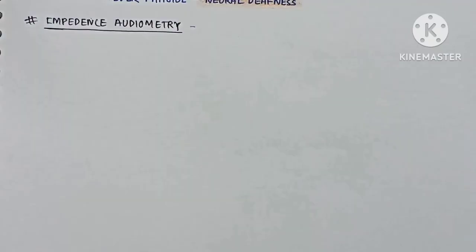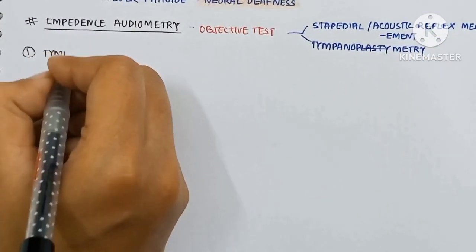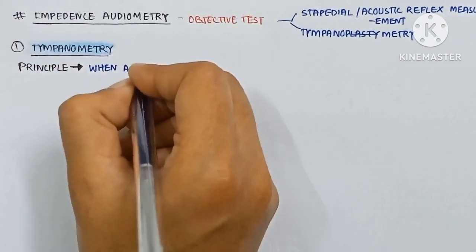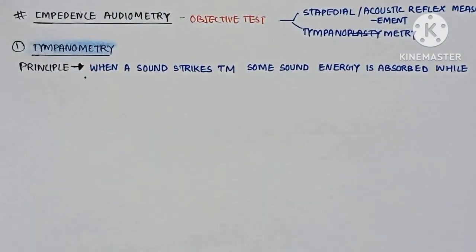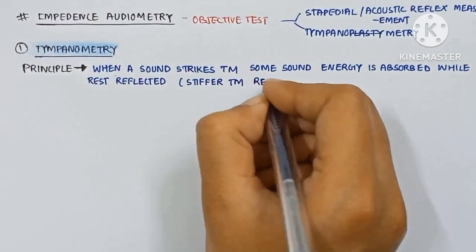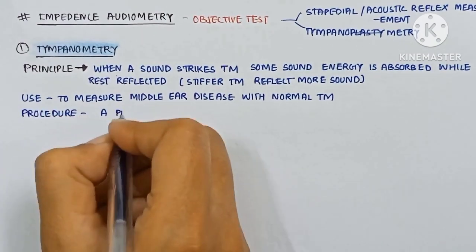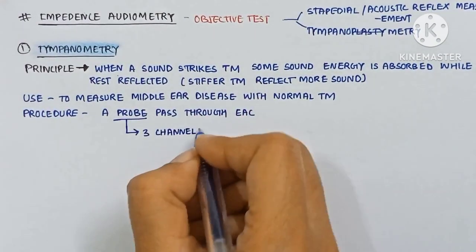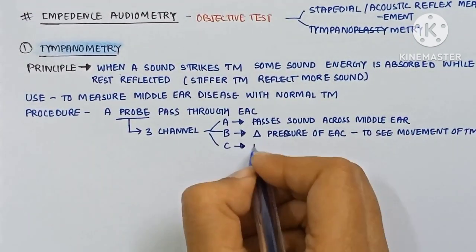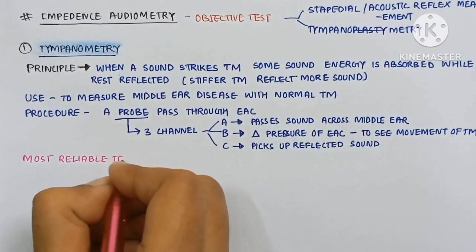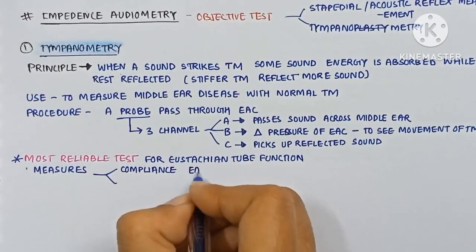Next is impedance audiometry. It is an objective test for stapedial reflex measurement and tympanometry. The principle of tympanometry: when a sound strikes the tympanic membrane, some sound energy is absorbed while the rest is reflected. A stiffer tympanic membrane reflects more sound. It is used to measure middle ear disease. The procedure: a probe is passed through the EAC with three channels — A for passing sound across the middle ear, B for changing pressure in the EAC to observe tympanic membrane movement, and C for picking up reflected sounds.